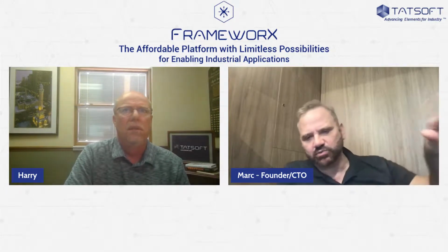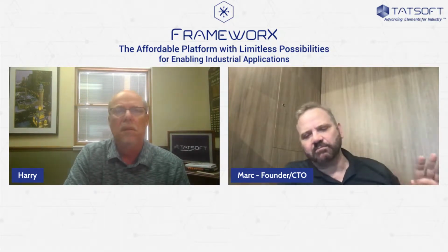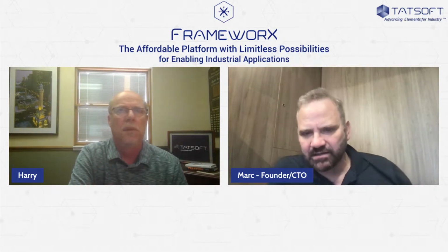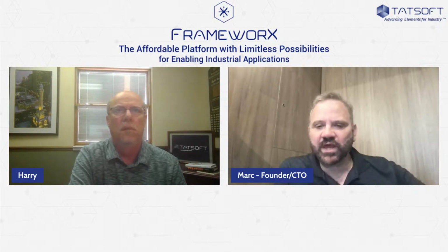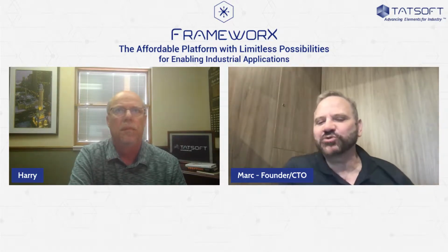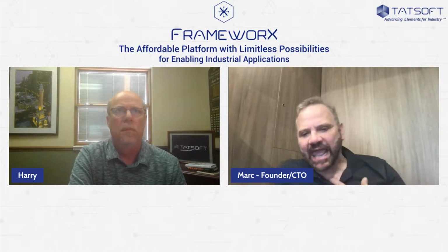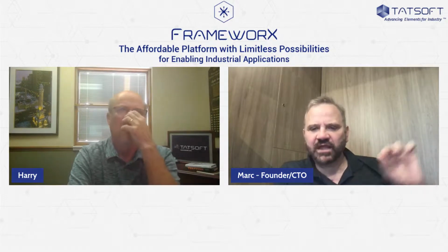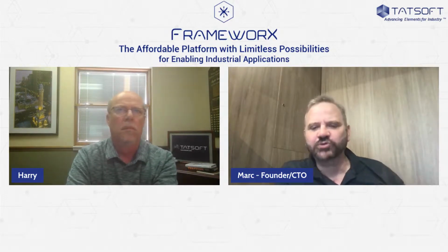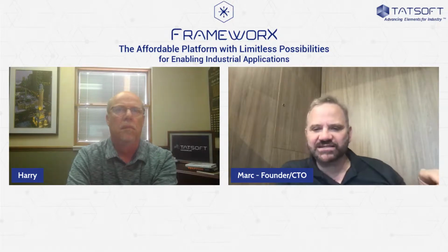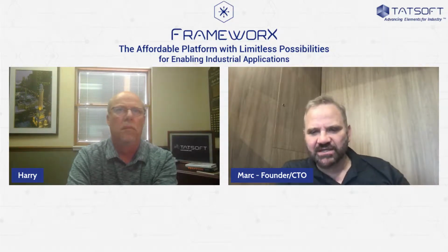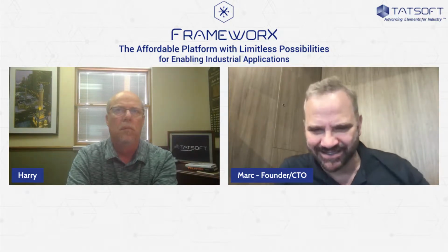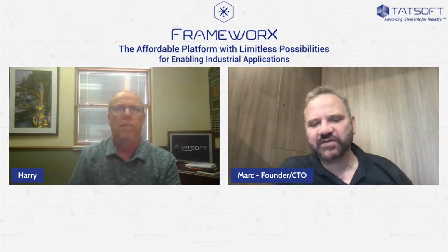The ControlLogix, which was not even listed on the main topic, is very important because to be able to put control logic as a tech provider, we have to have a very easy way to do the inspection of the variables, the ControlLogix. We had in the past the ability to read the L5K file and import the tag definition from ControlLogix. With this release, we are doing one step beyond that: you can browse the variables from the PLC memory. We don't need the L5K file anymore.